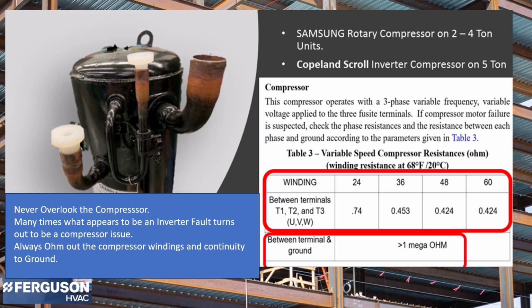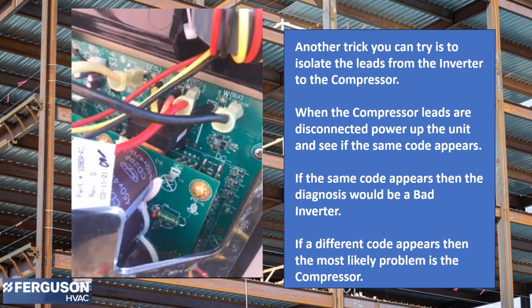Never overlook the compressor. Many times what appears to be an inverter fault turns out to be a compressor issue. Always ohm out the compressor windings and continuity to ground. Another trick you can try is to isolate the leads from the inverter to the compressor. When the compressor leads are disconnected, power up the unit and see if the same code appears. If the same code appears, then the diagnosis would be a bad inverter. If a different code appears, then the most likely problem is the compressor.